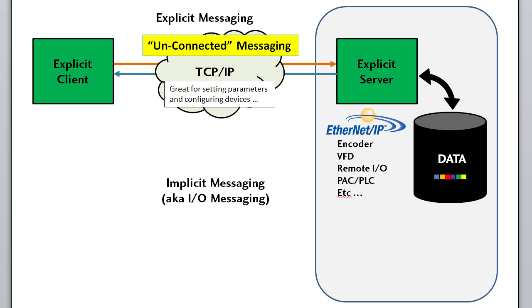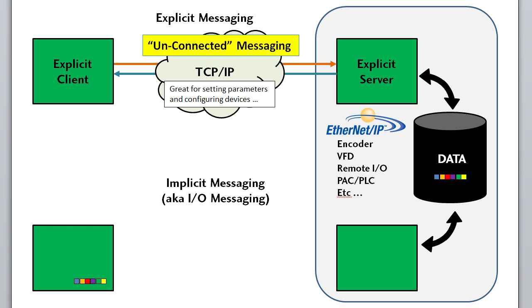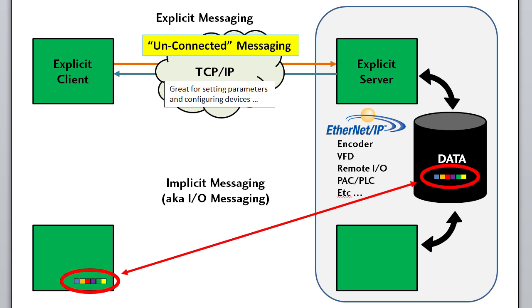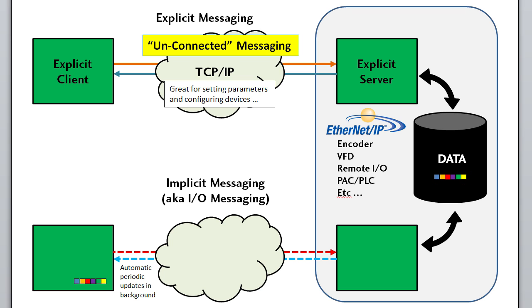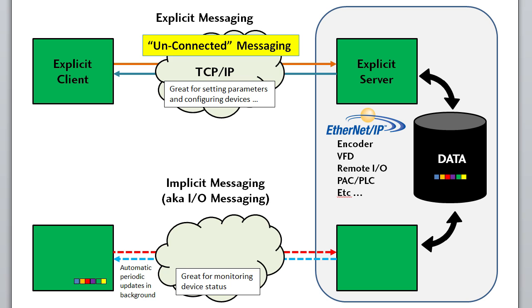Implicit messaging, on the other hand — which we also call I/O messaging — is time critical and is much more efficient. The reason it's more efficient is you preset up, or connect, both ends so they know implicitly exactly what to expect, without having to include the extra communication baggage in each and every message. The data is simply copied back and forth at a periodic rate in the background. You don't have to do anything once it's enabled — the data just appears on your local controller as if it was local I/O. This is ideal for things like monitoring the speed of a variable frequency drive.